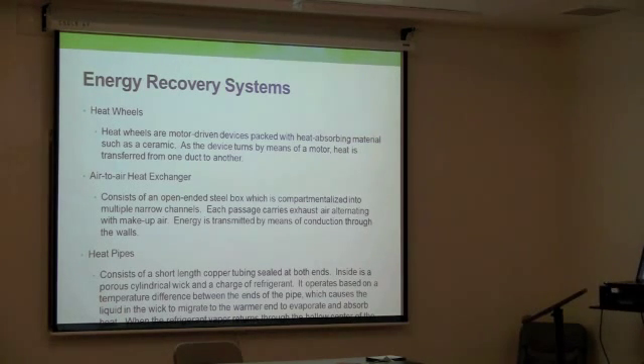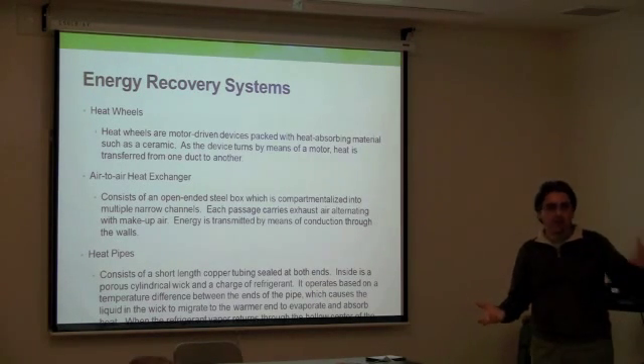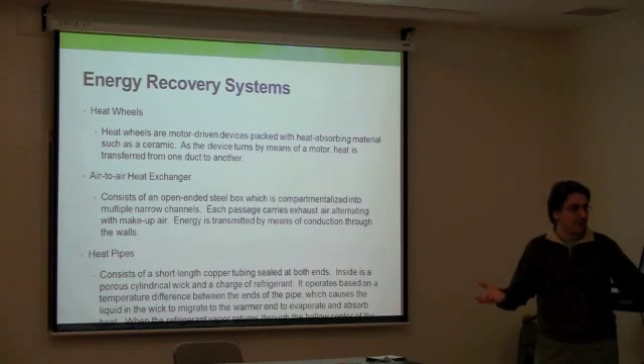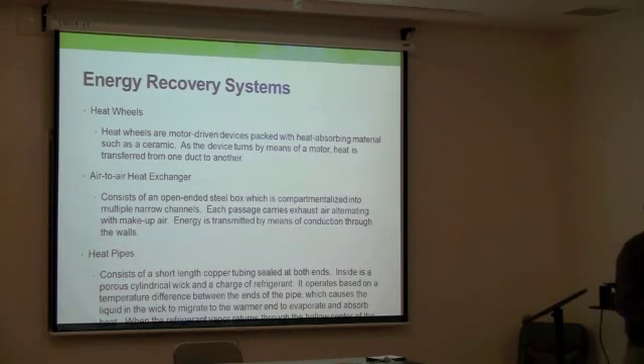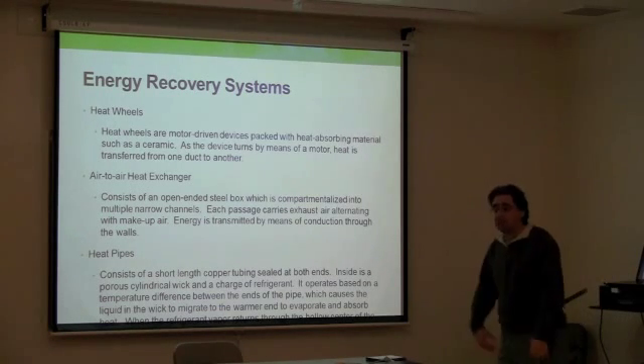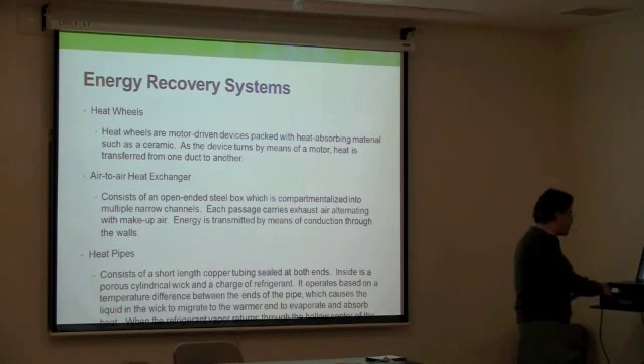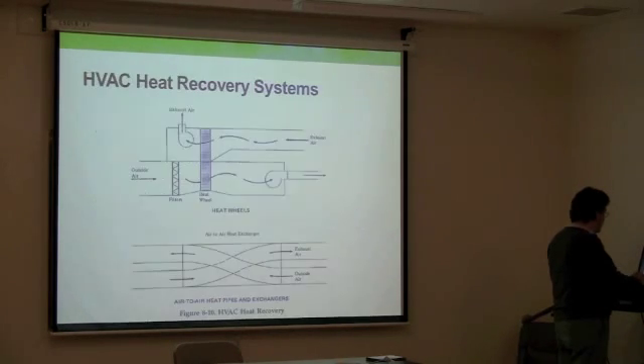Sometimes, even during winter and summertime, depending on the operation you have, and this happens a lot in the hospital, you need to have cooling and heating at the same time working. Right? There are rooms that need to be heated, there are rooms that need to be cooled. And so you don't want to have an air conditioning and a boiler at the same time working together for two different purposes. A lot of times you try to use devices in between in order to exchange heat from one area to another area. And there could be heat wheels, there could be air-to-air heat exchanger, heat pipe can be used. There are many devices in order to transfer heat from hot area to a cold area.